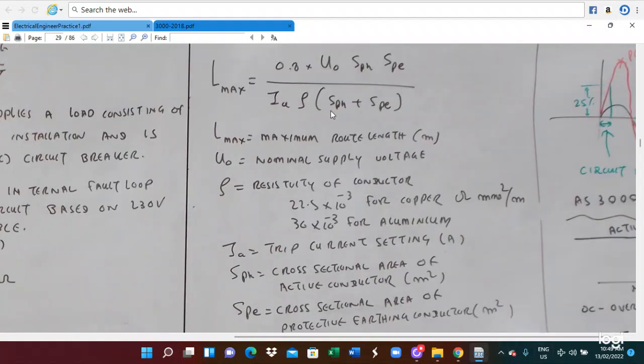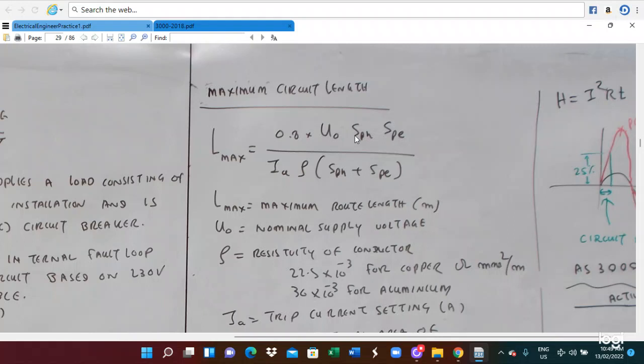The next one is we also have to decide the maximum circuit length. So what should be the maximum circuit length? So we utilize this formula. L maximum is 0.8 multiplied by U0 SPH SPE divided by IA rho SPH plus SPE. L maximum is the maximum route length of your cable. U0 is the normal supply voltage. Rho is the resistivity of the conductor.